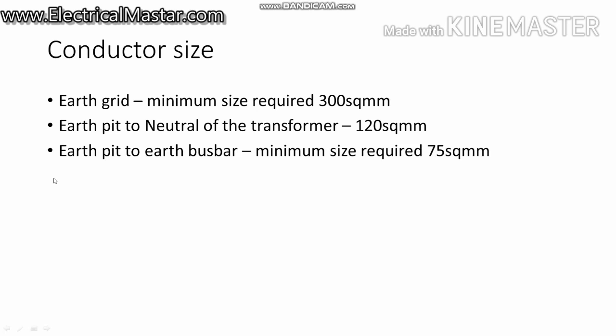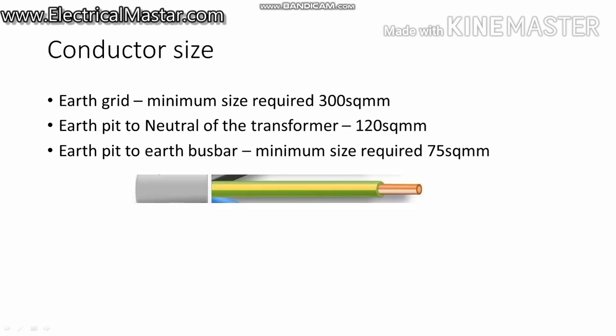And third is the earth pit to earth bus bar. This is the incomer of the earth bus bar supply. You have to use a minimum cable size of 75 square mm, and here you can use PVC yellow-green coated cable, which is acceptable.